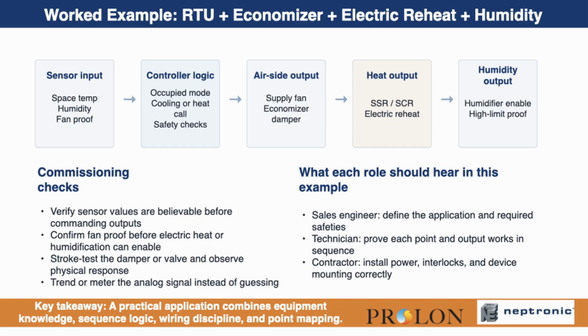This example is important because every step depends on the one before it. If the fan proof fails, electric heat and humidification should not be allowed to operate. If the sensor values are not believable, the controller decisions will be wrong. And if the outputs are commanded but the physical device does not respond, the process will not stabilize. This is exactly why we say a practical application combines equipment knowledge, sequence logic, wiring discipline, and point mapping.